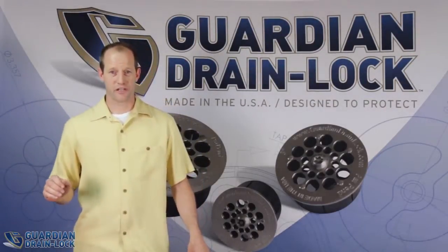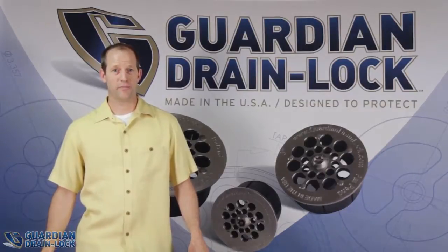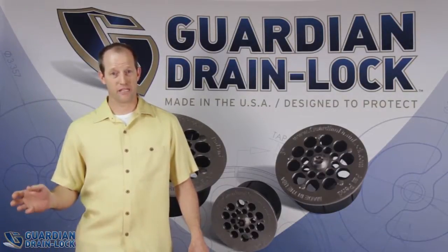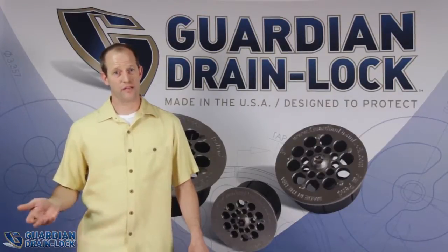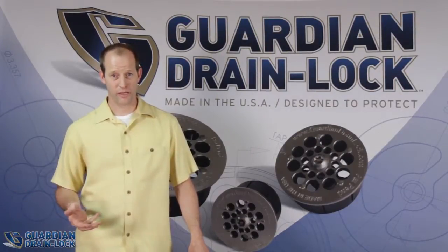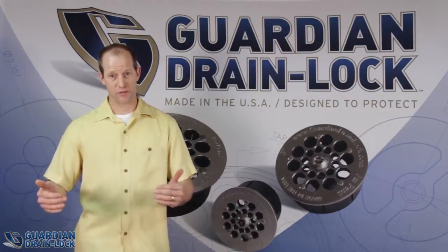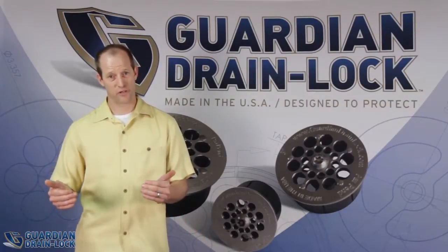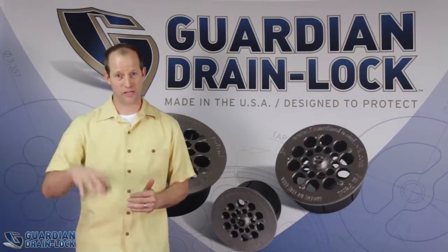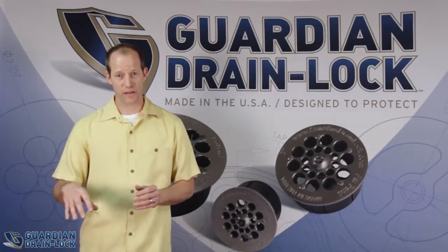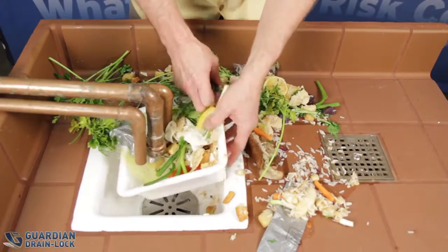What General Construction does when they build a restaurant is they don't care about making it easy for the operator to use a floor sink and to service it. The only thing they care about is putting it in per code. And what that means is a lot of times they put this in such a manner that a floor sink is way underneath the kitchen equipment, or the pipes are so on top of the floor sink with very little gap you can't even service it. You can't even pull the basket out.